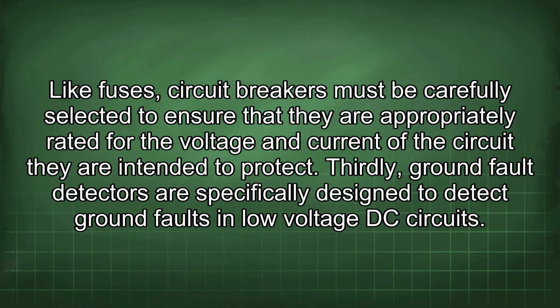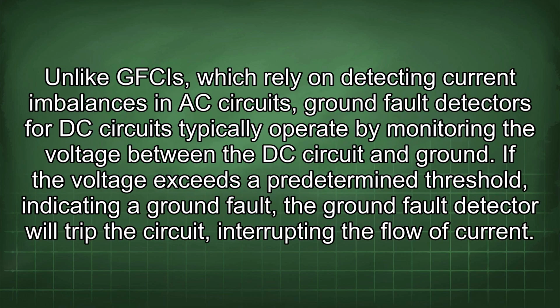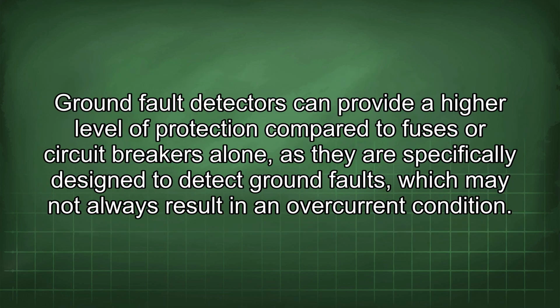Thirdly, ground fault detectors are specifically designed to detect ground faults in low-voltage DC circuits. Unlike GFCIs, which rely on detecting current imbalances in AC circuits, ground fault detectors for DC circuits typically operate by monitoring the voltage between the DC circuit and ground. If the voltage exceeds a predetermined threshold, indicating a ground fault, the ground fault detector will trip the circuit, interrupting the flow of current. Ground fault detectors can provide a higher level of protection compared to fuses or circuit breakers alone, as they are specifically designed to detect ground faults, which may not always result in an overcurrent condition.